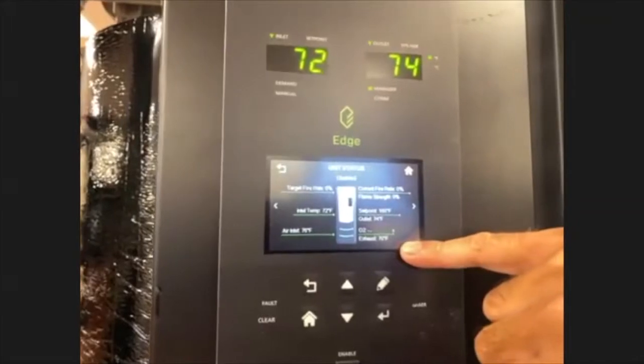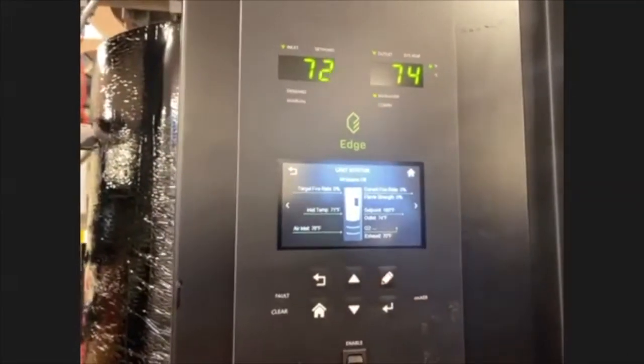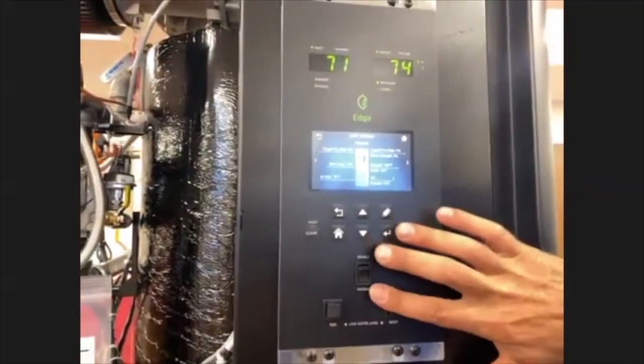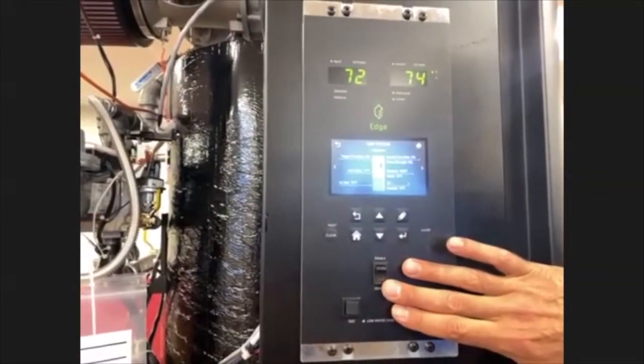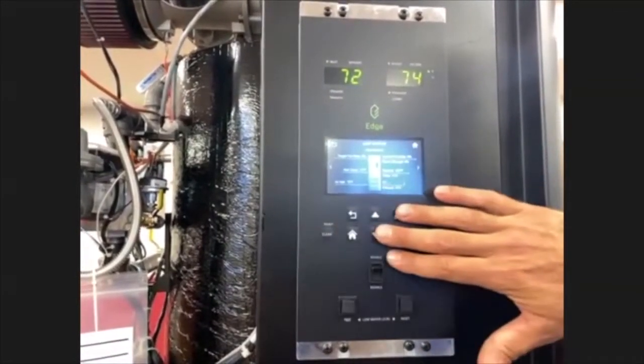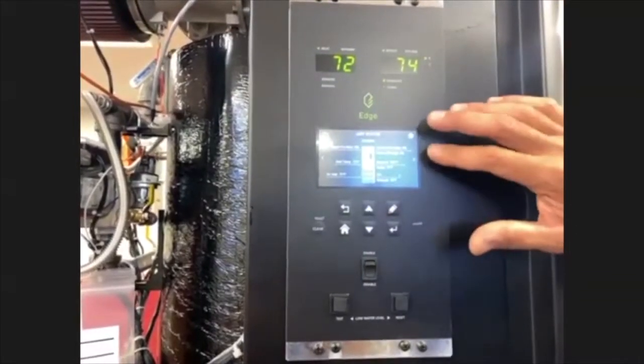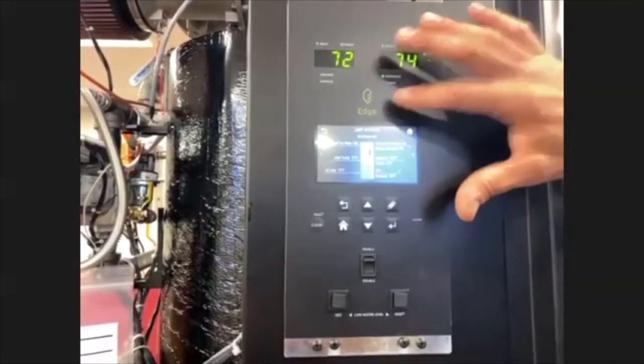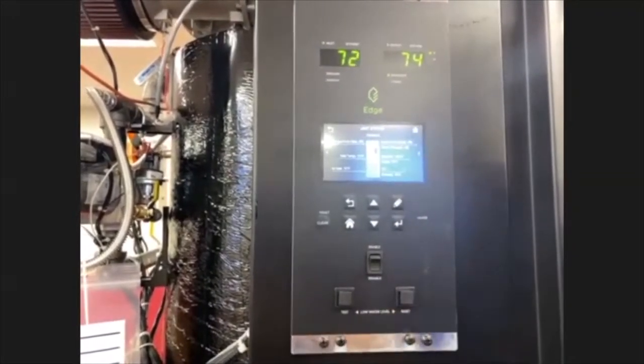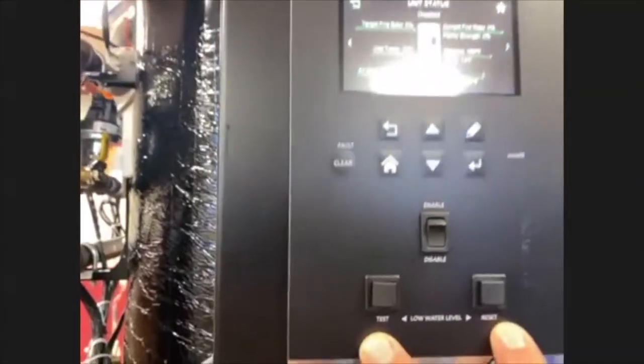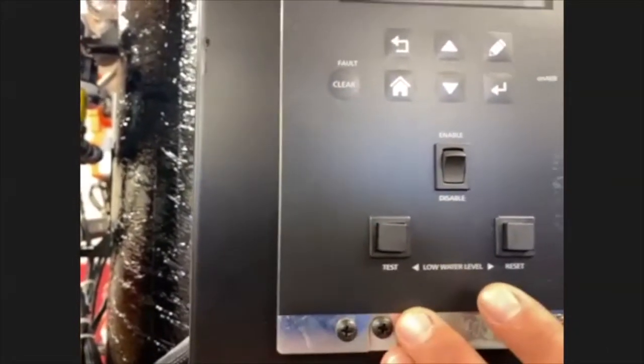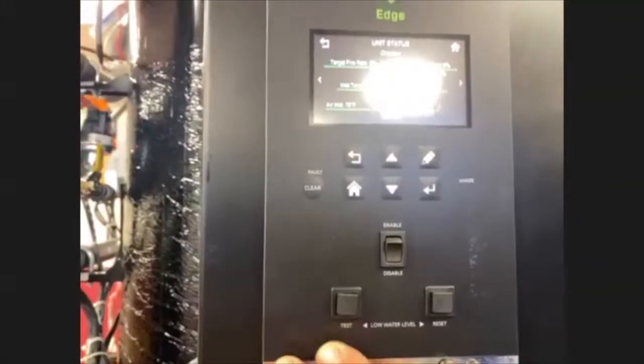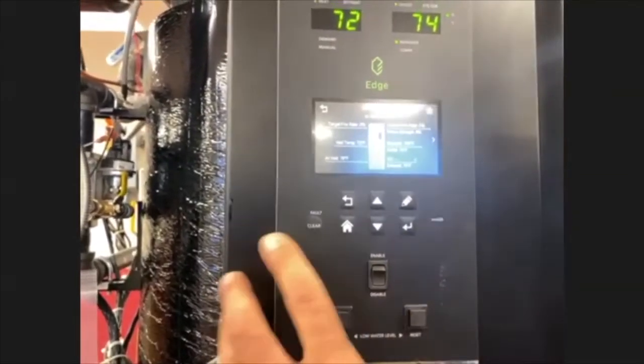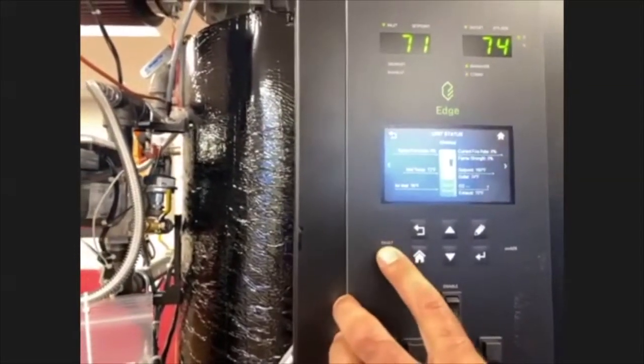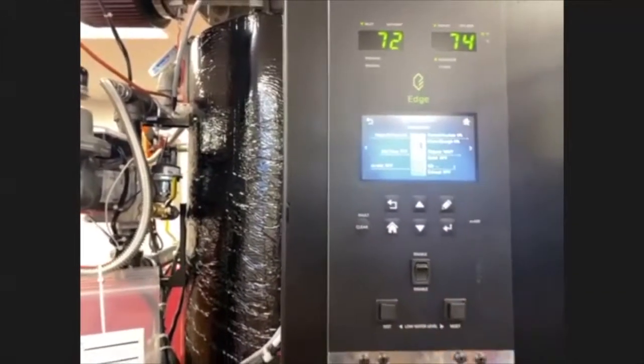We also have our exhaust temperature and our air inlet temperature. Enable disable button. This will start and stop the boiler. And then we have a series of keys here as well that will allow us to scroll through menus and different variables and settings inside of the controller, inside of the Edge controller. We also have our low water cutoff, test, and reset buttons here. So test button, reset. If you ever perform a test or you ever trip a low water cutoff, you will need to correct the problem, manually reset it here before clearing the fault here. If you just simply try to clear the fault, it will still stay there unless you do a manual reset.